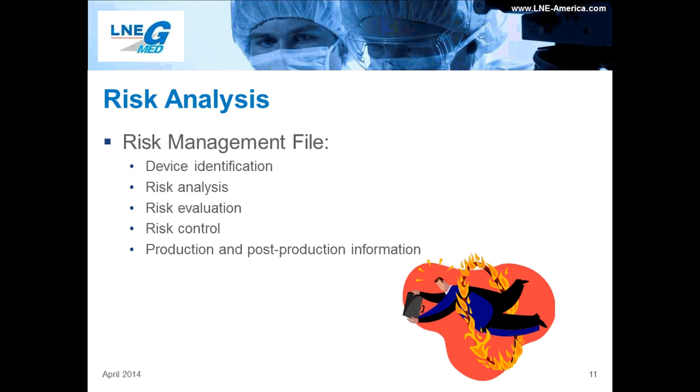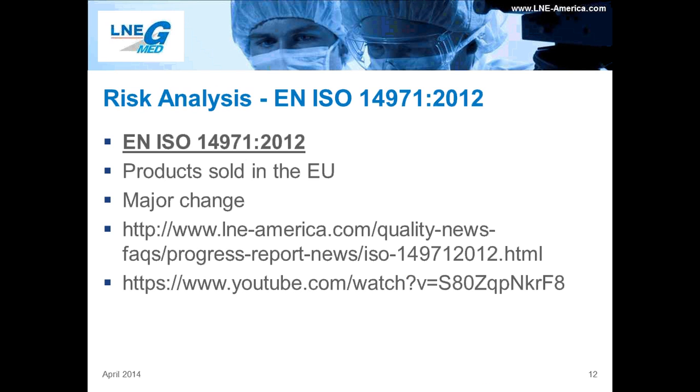And I thought this picture was rather appropriate because when it comes to risk management, many organizations feel as if they are constantly jumping through hoops. And for that, we can thank, you guessed it, ISO 14971, revision 2012. So I decided to dedicate a slide to this standard alone because this is one of the most common nonconformities we're currently seeing in design dossiers and technical files.